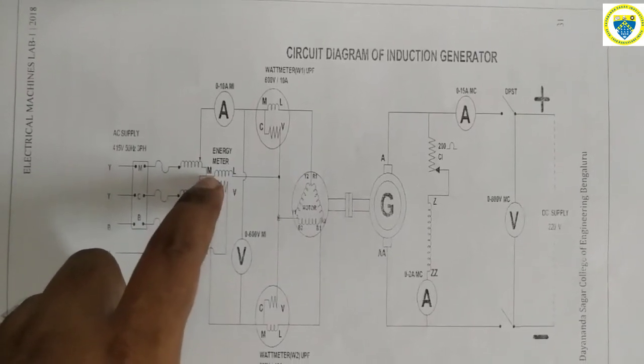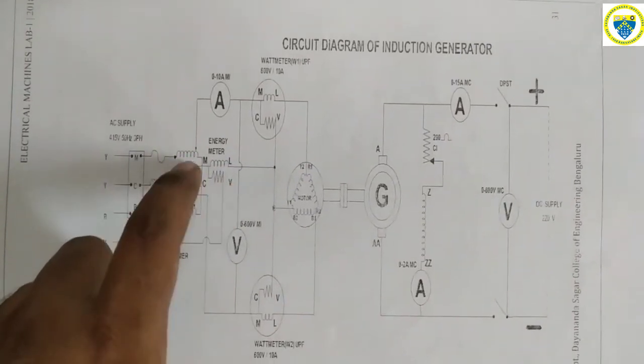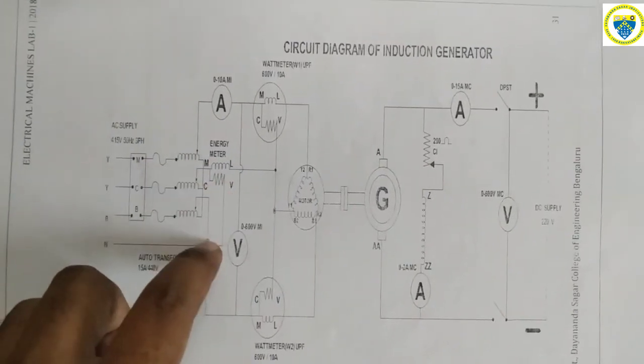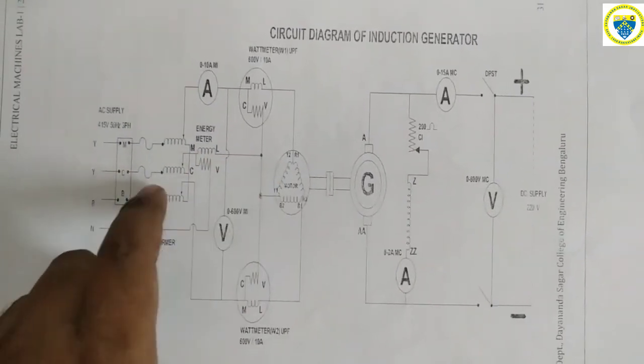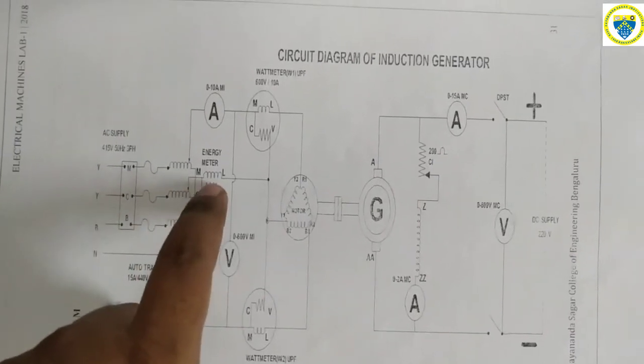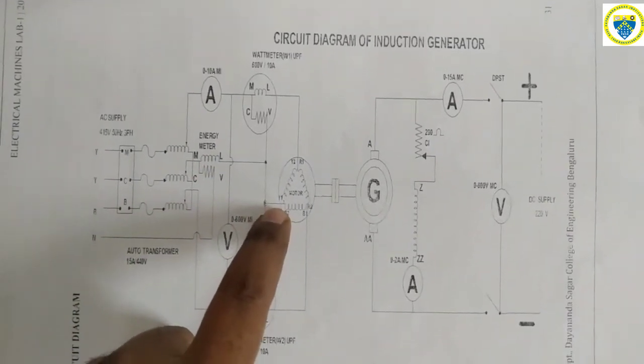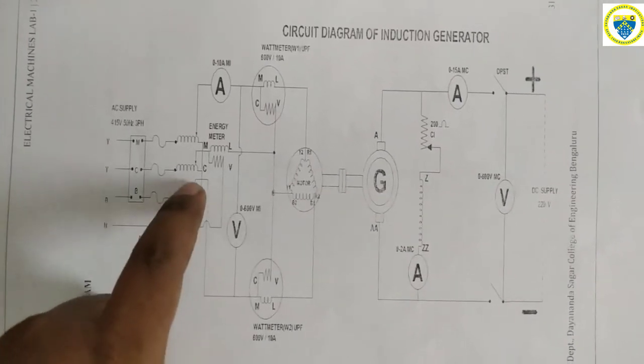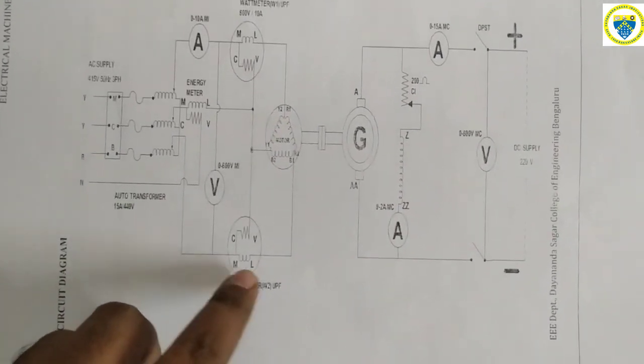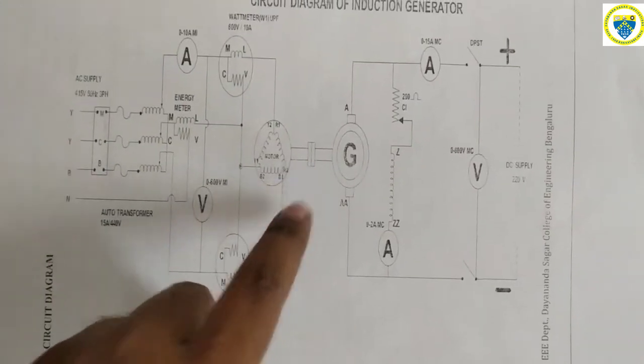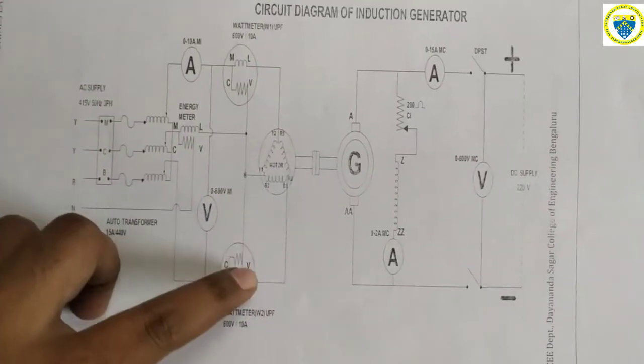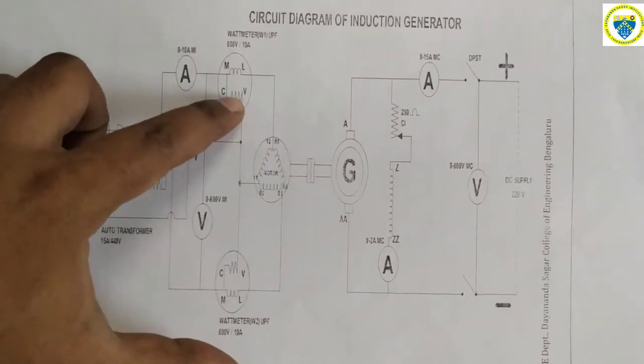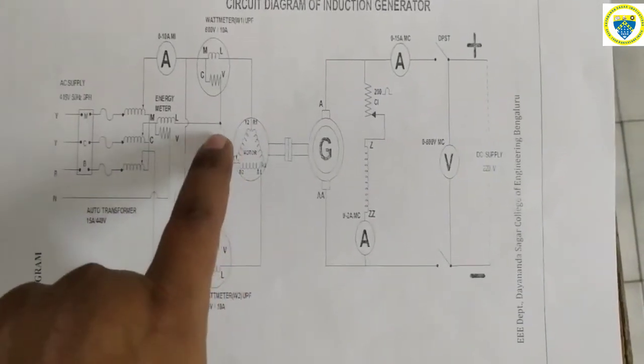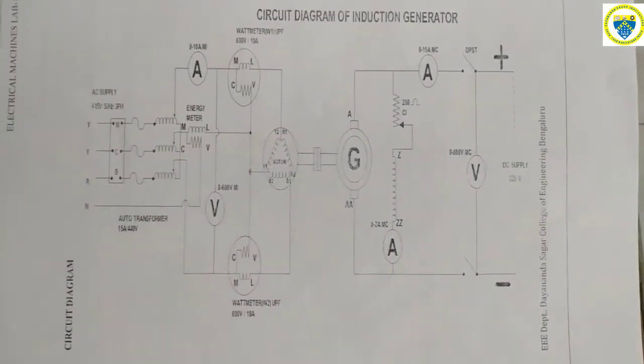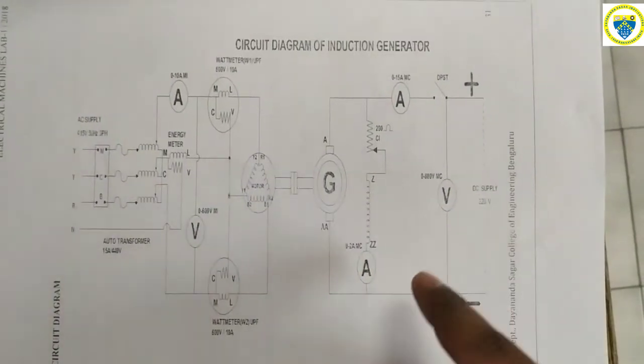In the energy meter also we will be having M, L, C, V terminals: mains, line, common and voltage terminals. So here also the Y phase should be sent through this energy meter, and it should be given to the second terminal of the stator. Again the third terminal, B phase, should go to the M terminal of wattmeter 2, and then L should go to the third terminal of the stator. Here the very important connection is that the V of wattmeter 1 and wattmeter 2 should both be shorted, and shorted to the second terminal of the stator, and the same terminal should go back to the energy meter. And here also we have the normal connections with respect to the generator.